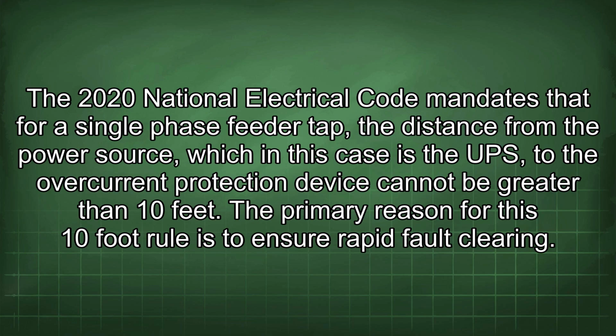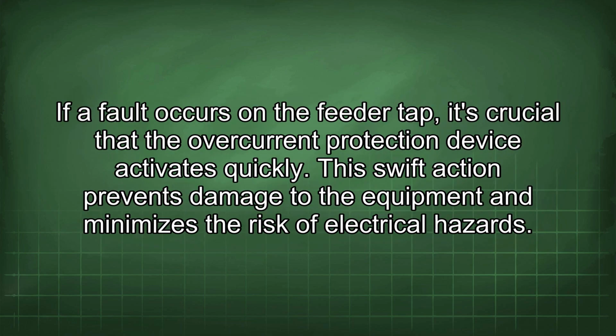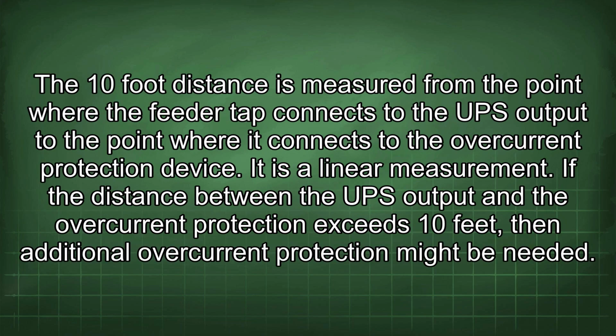The primary reason for this 10-foot rule is to ensure rapid fault clearing. If a fault occurs on the feeder tap, it's crucial that the overcurrent protection device activates quickly. This swift action prevents damage to the equipment and minimizes the risk of electrical hazards. The 10-foot distance is measured from the point where the feeder tap connects to the UPS output to the point where it connects to the overcurrent protection device. It is a linear measurement.